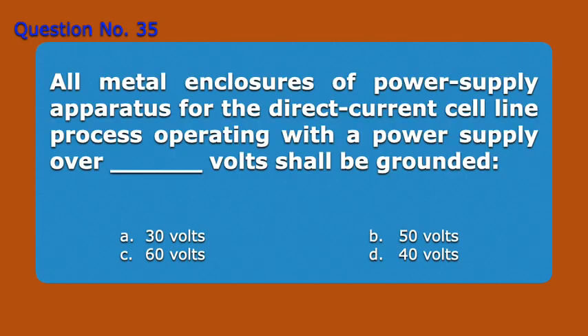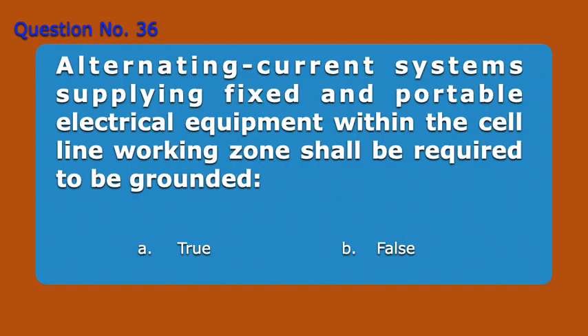Question number 35. All metal enclosures of power supply apparatus for the direct current cell line process operating with a power supply over blank volts shall be grounded. A. 30 volts. B. 50 volts. C. 60 volts. D. 40 volts. Answer B. 50 volts. Question number 36. Alternating current systems supplying fixed and portable electrical equipment within the cell line working zone shall be required to be grounded. A. True. B. False. Answer B. False.